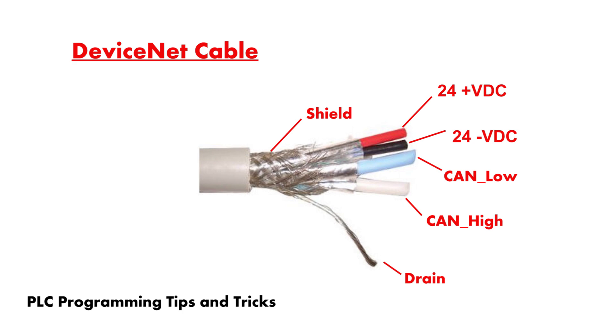As you can see the cross section of the DeviceNet network cable, it has five conductors inside. Black is a common cable and blue is a CAN low cable. Uninsulated cable is a drain cable and we have to earth this cable. The white is a CAN high cable and the red cable is a power supply positive voltage. The red and black cables normally carry 24 volt DC.